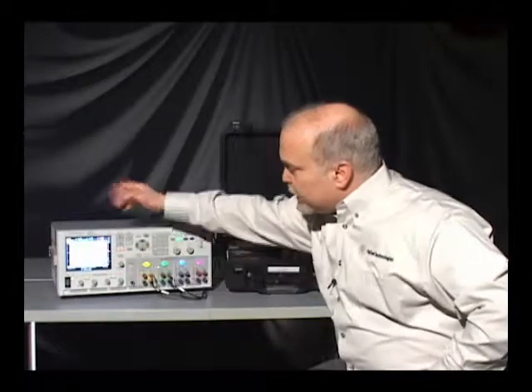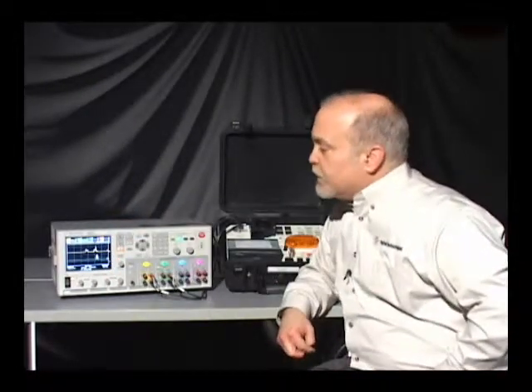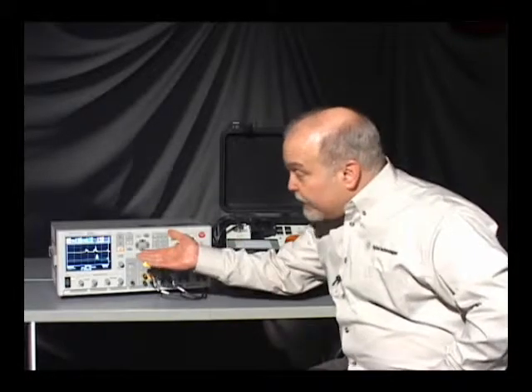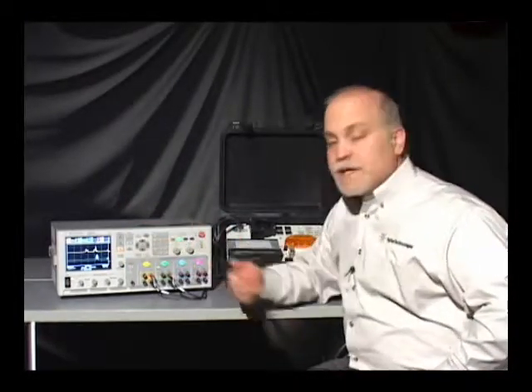OK. So, 30 seconds is up. It saved the file. And now, you can see the waveforms. Now, once I have this data collected, I can do different things with it. I can save this picture as a bitmap and I can import it into a report. Or I can export the data as a CSV file and then analyze it with some other software.